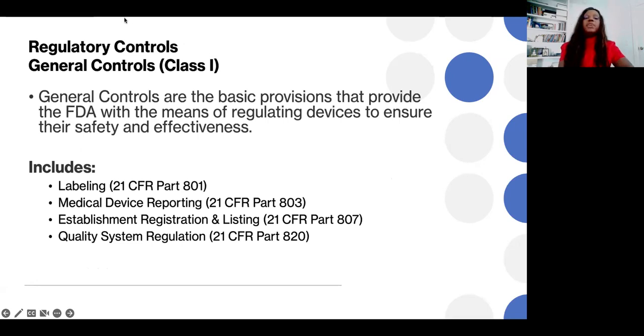Yes, so for regulatory controls, we have what we're calling general controls. These are the basic provisions that provide the FDA with the means of regulating devices to ensure their safety and effectiveness. So these include, for example, that all products must have labeling. So they must have a package insert that explains to the user how to use the product. And the regulation that's applicable for labeling is 21 CFR Part 801.